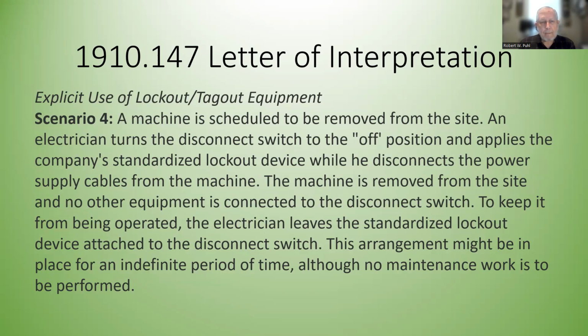Scenario 4. A machine is scheduled to be removed from the site. An electrician turns the disconnect switch to the off position and applies the company's standardized lockout device while he disconnects the power supply cables from the machine. The machine is removed from the site and no other equipment is connected to the disconnect switch. To keep it from being operated, the electrician leaves the standardized lockout device attached to the disconnect switch. This arrangement might be in place for an indefinite period of time, although no maintenance work is to be performed.